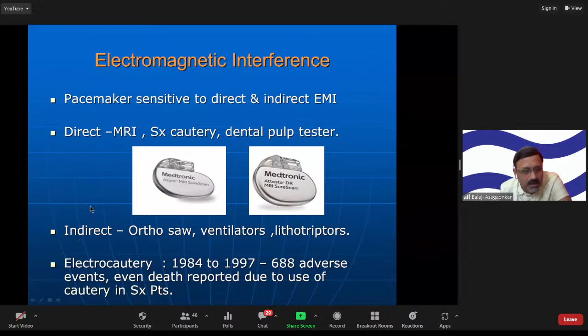Now, how to go about it? Use bipolar cautery as much as possible, because the circuit is completed at that level only. If at all you want to use unipolar cautery, the ground plate should be close to the operative field. Suppose you are doing hernia surgery, just put the ground plate below the buttock so that the circuit will be completed. So unipolar cautery can be used. The pacemaker should always be put on an asynchronous mode. How to do it? We have to call a pacemaker company person inside the OT, or one day prior, or in the morning on the day of surgery, and put that pacemaker in asynchronous mode. And then cautery should be used.